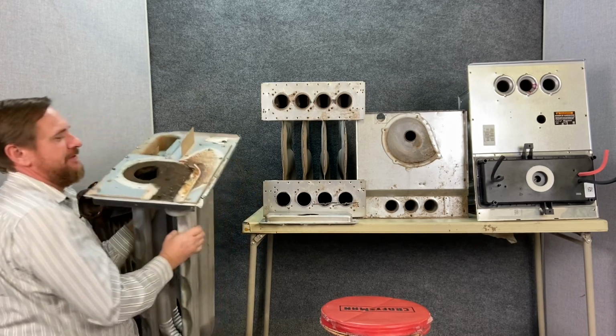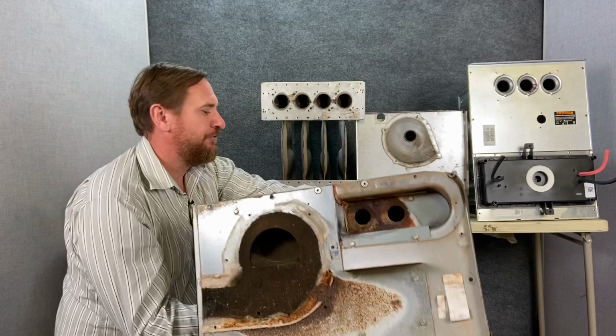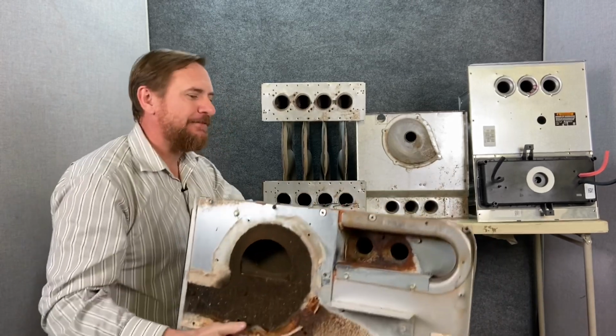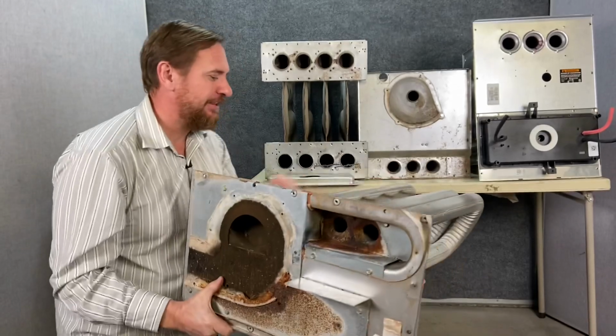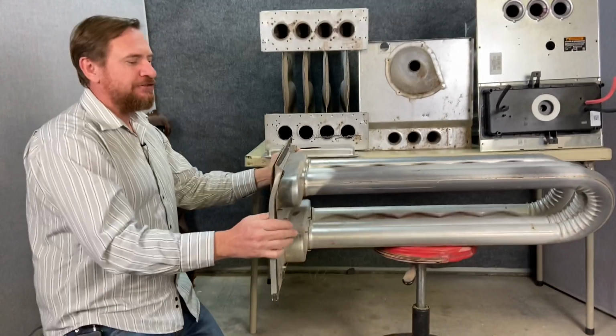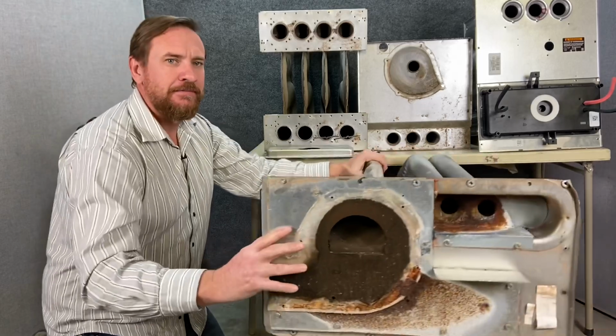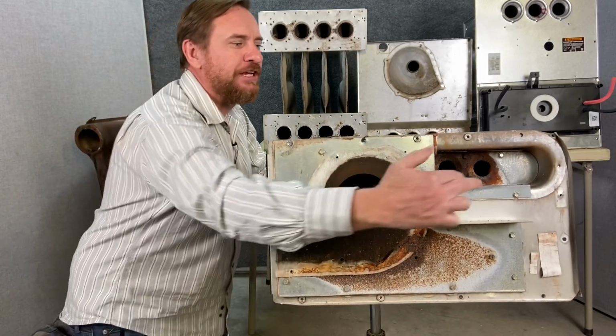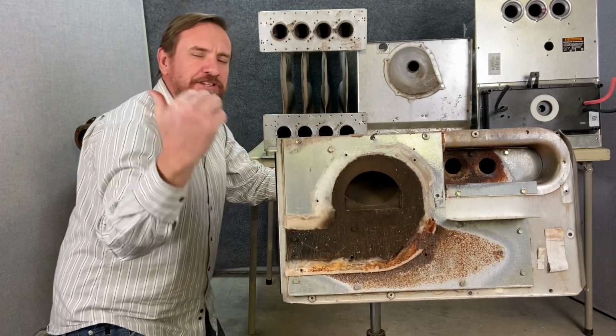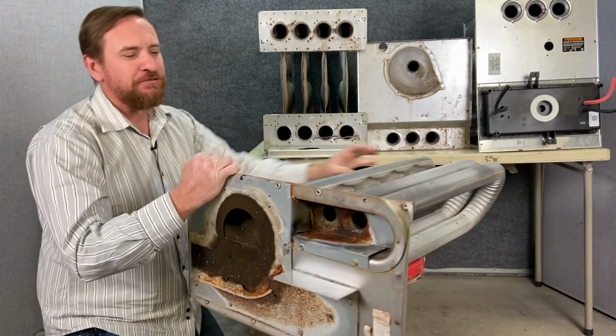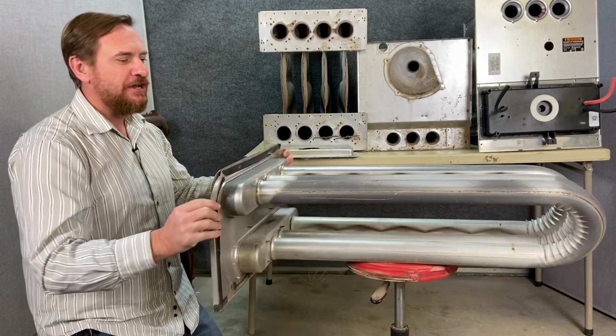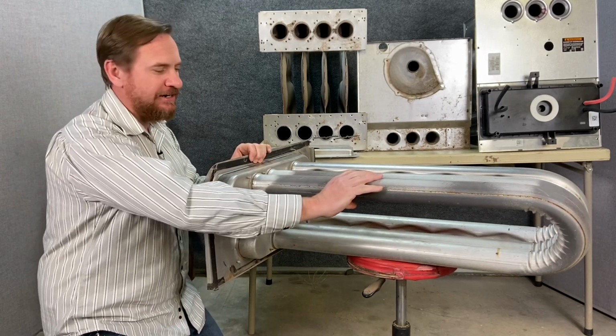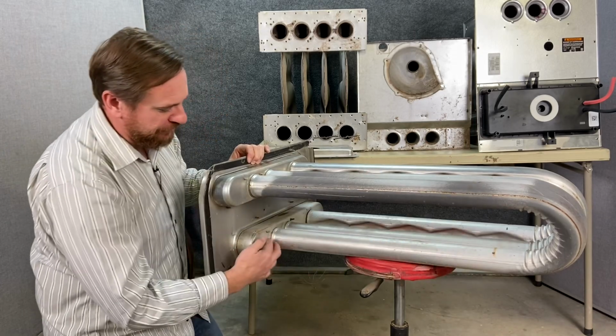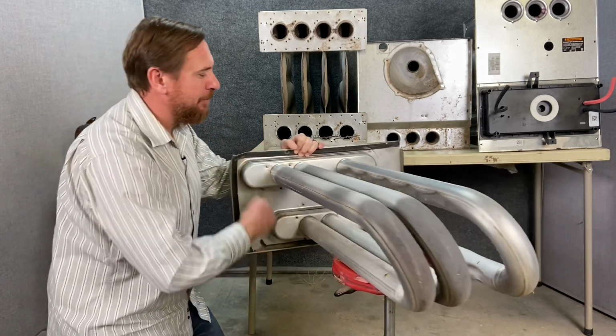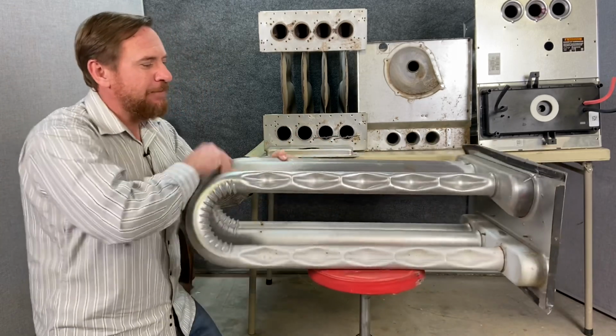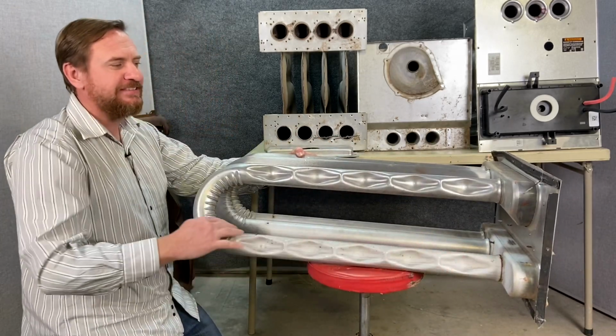Next, we came out, this is out of a package unit, an induced fan style heat exchanger. This particular one was installed in a package unit. So there'd be an inducer fan motor here pulling a draft through the heat exchanger and then forcing the combustion gases outside. What's really unique about this is a two burner heat exchanger, but we had our combustion chamber burning in right here, and it pulled the gases down through this little collection box at the bottom. From there, we pull those gases through this collection box again through this secondary pipe.